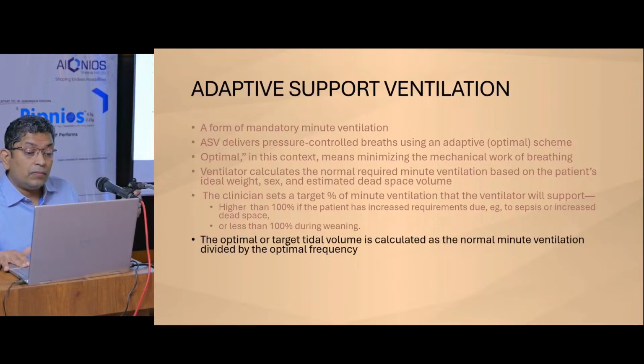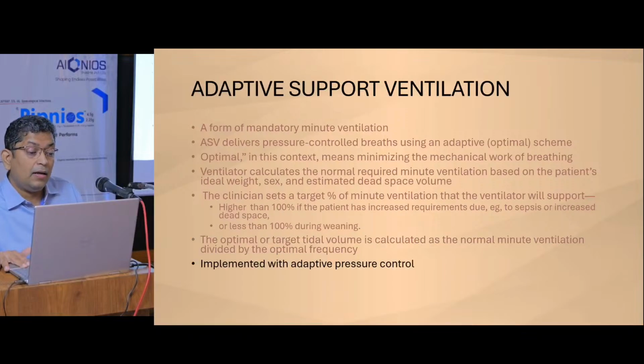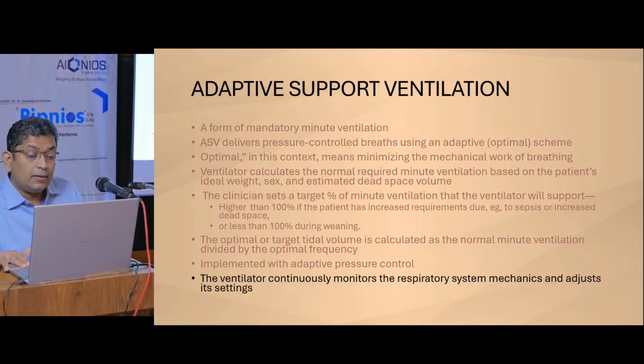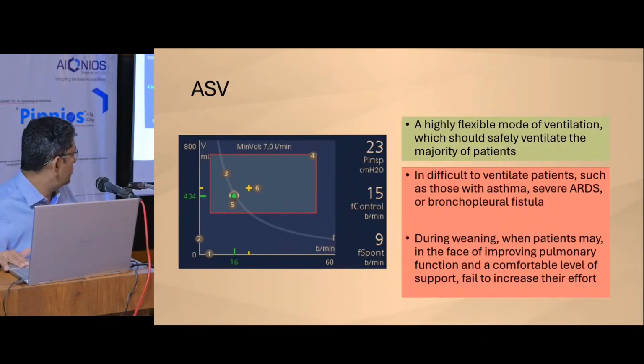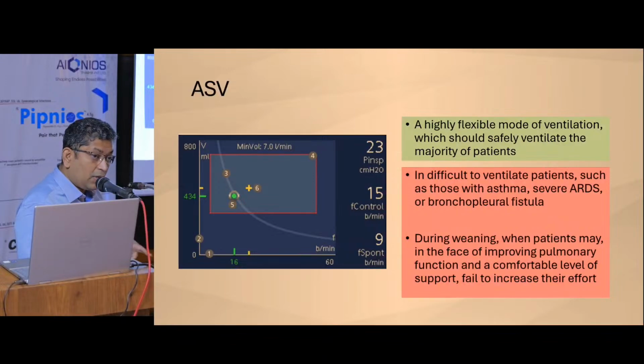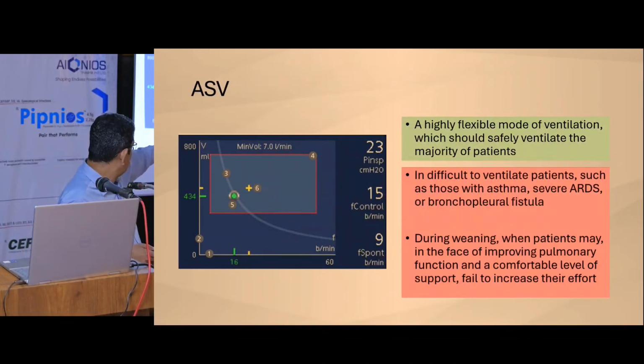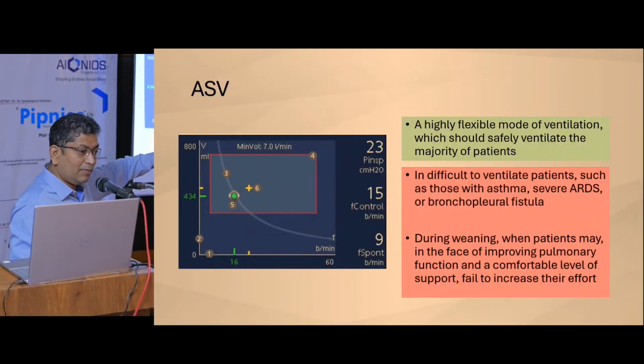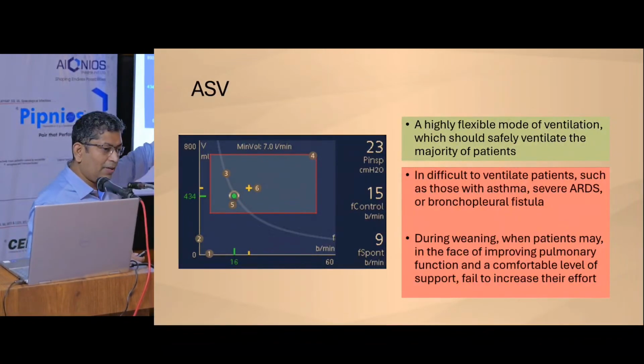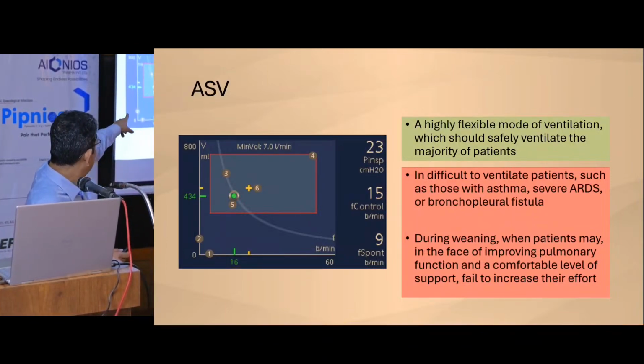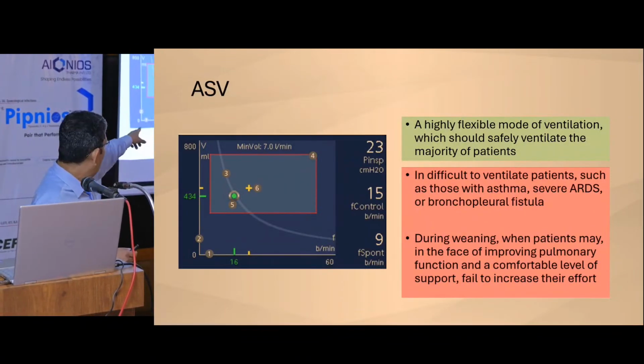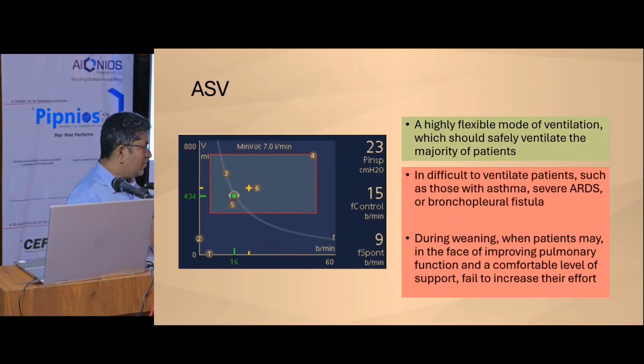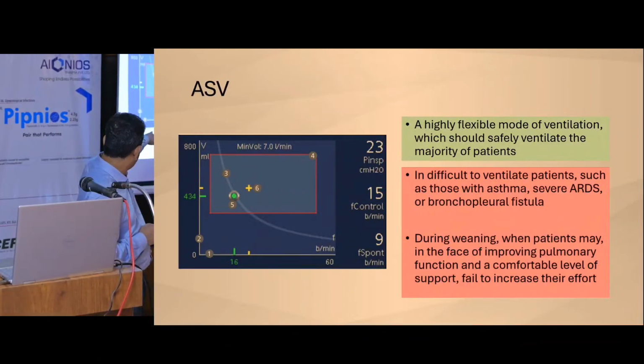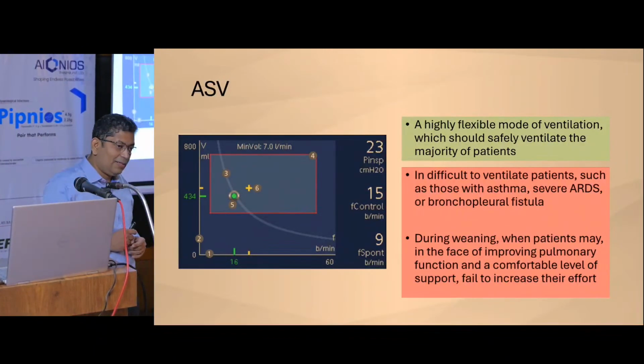So the tidal volume is calculated by the normal ventilation divided by the optimal frequency, and it is implemented. Let me show you how it's done. This is the Otis curve. With each respiratory rate, the tidal volume needed is calculated. You look at the minute volume and it calculates the tidal volume and the respiratory rate, and the minimum energy is found, and that's the green dot there. So for this patient, it's around 16 breaths and around 400 tidal volume.